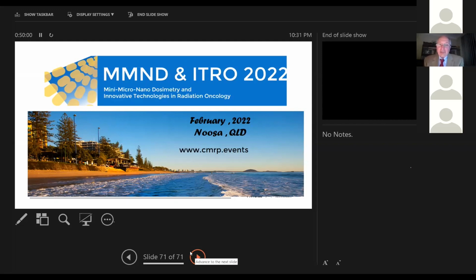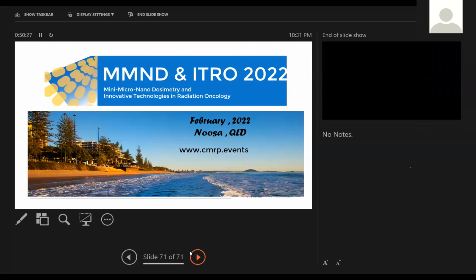Okay, the major advantage of the MOSkin detector is that you can measure skin dose at a depth of 70 micron reproducibly. No other detector exists which can measure skin dose unless you put film, and film requires a long time for processing. All detectors need to be reproducible, as you remember, it's required to measure at a depth of 0.07 millimeter. And they're disposable detectors. You put them in the garbage, you don't need to worry about them. And currently they will be wireless for the patient on the skin. You can put them, and they don't even need power. They're like TLD, but measuring skin dose immediately.